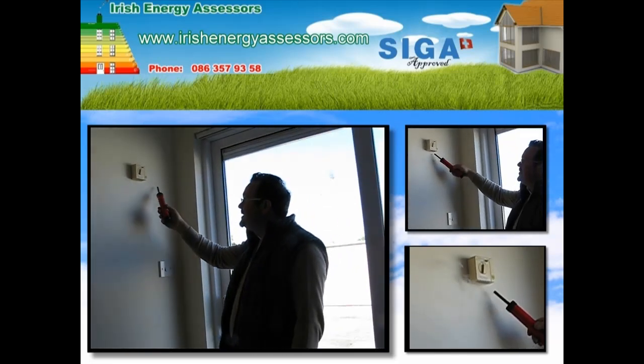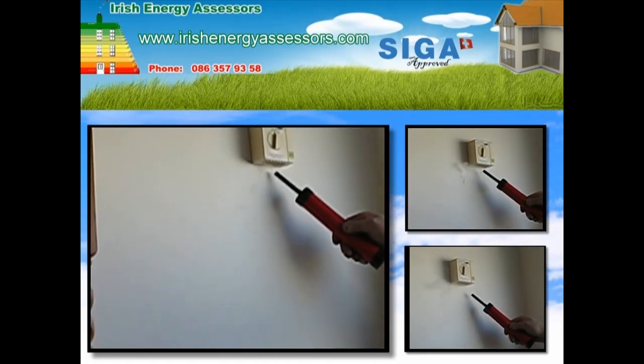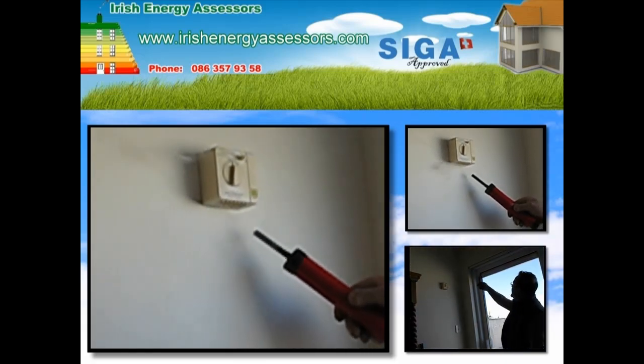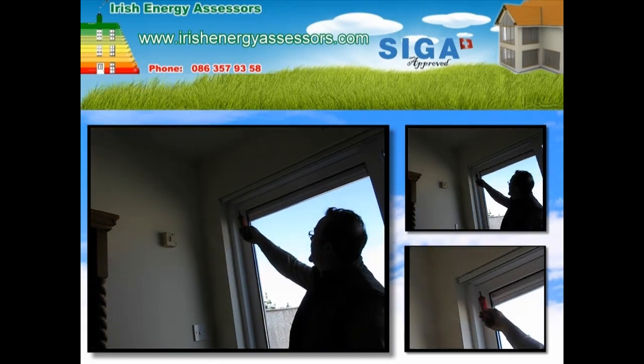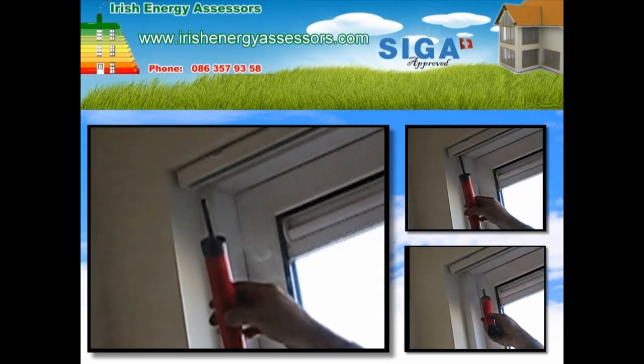which happens a lot on existing houses. The thermostat here on the wall — you can physically see the hole around it. I'll just pop the smoke detector here so you can see how much air has been sucked in around that hole. It's actually blown away from it — quite a lot. The corner of these double doors up here, a little bit, but it still adds up.